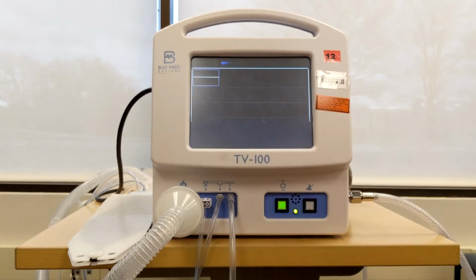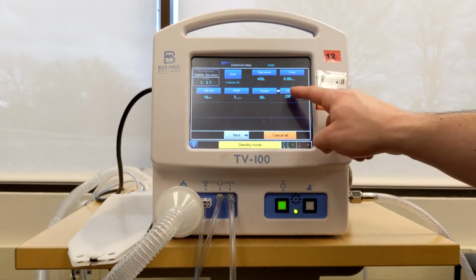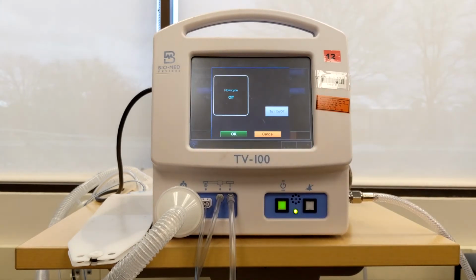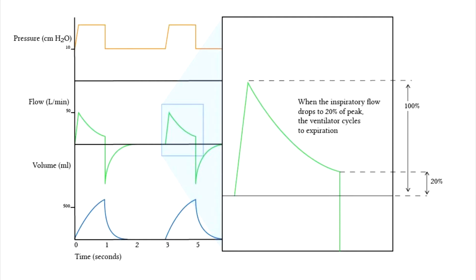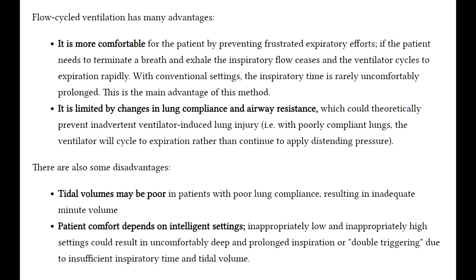Now that we're using a flow sensor, we are able to use certain instruments like flow cycling. With flow cycled ventilation, the ventilator cycles into the expiratory phase once the flow has decreased to a predetermined value during inspiration. The flow cycling variable can be a fixed flow value in liters per minute or a percentage fraction of the peak flow rate achieved during inspiration. With the TV-100, this variable will be a fixed flow value in liters per minute.